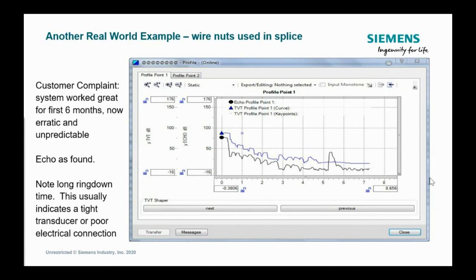This system had been in operation a little more than 6 months, and they were having some challenges with it. And I looked at this echo profile, and what you note is it doesn't really ring down to the noise floor. It takes a long time for this thing to ring down before it gets down to the noise floor, and finally you get this echo. And I looked at this, and I said, okay, where is the transducer cable spliced? And they said, oh, no, it's not spliced. It's continuous. I said, no, I'm looking at the cable coming into the box. That's not my cable. And I know the transducer has a cable coming out of it. Somewhere it's spliced. And they said, well, how do you know it's spliced? I said, well, it's not the same cable. And number two, I can tell by looking at the echo profile, you've got this thing spliced, and I'm going to bet you used wire nuts. This happened to be a wastewater application.